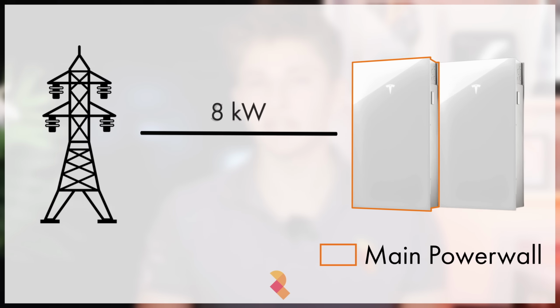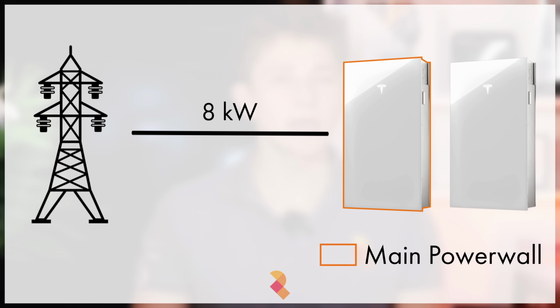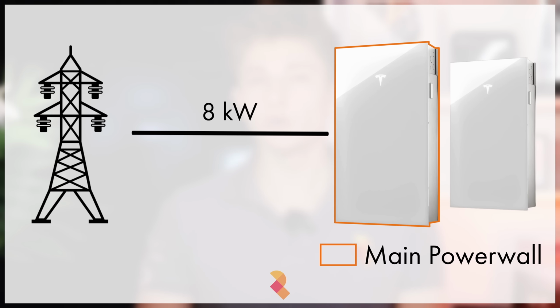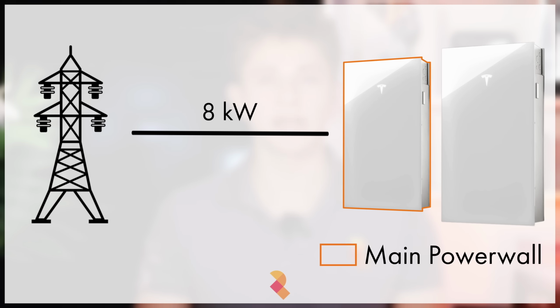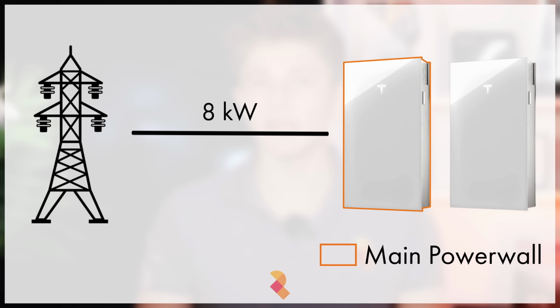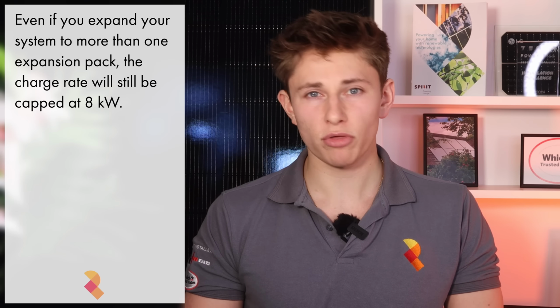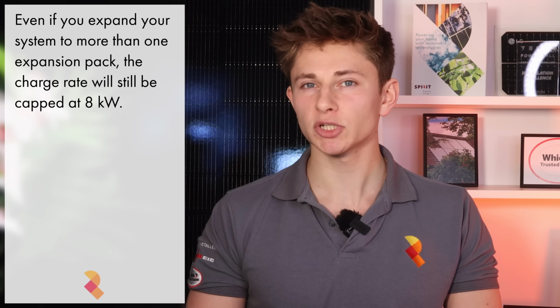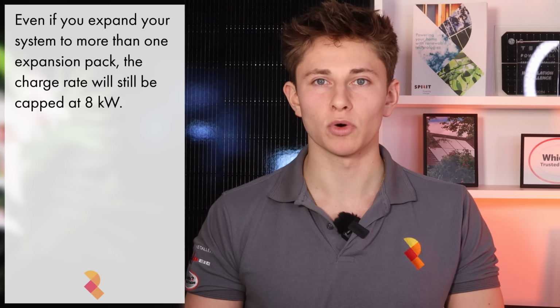If you add a DC expansion pack onto your Powerwall 3, then the maximum charge rate does increase up to 8 kilowatts. So with 1 Powerwall 3 and 1 expansion pack, the combined system can charge at 8 kilowatts, with the charge distributed evenly across the entire system. The main unit and any expansion packs will charge in sync. However, the charge rate doesn't scale beyond this - even if you add 2 or 3 expansion packs, the maximum charge rate remains capped at 8 kilowatts.